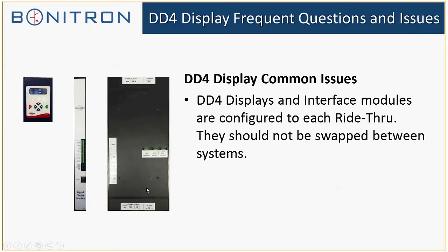This is the interface module, and it interprets the signals from the ride-through and outputs it to the display. What we've seen is that customers will just swap out these interface modules and displays. They might have a sag system and they'll try and put it into a system that's meant for ultracaps or batteries, depending on what they have, thinking they were able to fix it. But honestly, it just makes the situation a little bit more complicated, because the way we test these interface boards is we calibrate them for each individual ride-through before they leave.